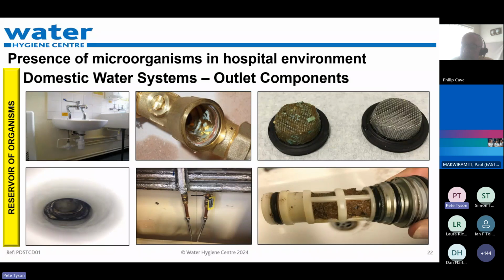So a TMV blends hot and cold water to make it a safe temperature. Where there are multiple TMVs, we are allowing more components with a low temperature of hot water to be a potential source. Thermostatic mixing valves can mix temperatures to 38 to 44 degrees centigrade, and Legionella bacteria grow fastest at 37, body temperature. 38 degrees C is not too far away from that, so it's a potential area where Legionella bacteria can form.